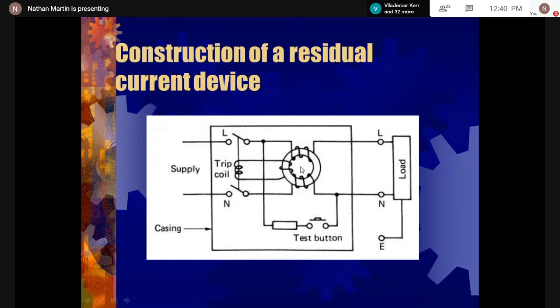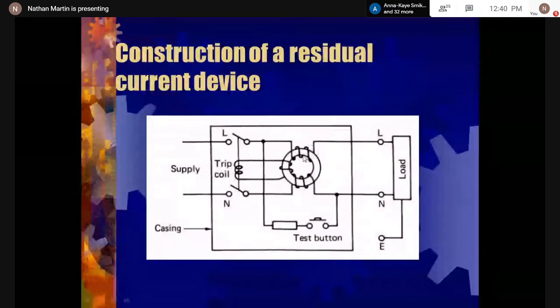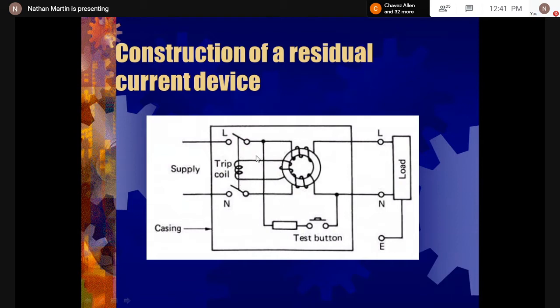Two coils, let me say it again, one with the current flowing in one direction, the other in the other direction. When the magnitudes are the same, the resultant is 0. There is no induced voltage. Now, if we have a short circuit to ground, then the current flowing into the device and the current flowing out of the device to the return, that's the neutral, will be opposite, but of different magnitude. Hence there will be a resultant, and that resultant will produce an induced voltage in the trip winding. Because it creates a closed path, you will have a current flowing. And this current, because of how it's designed with this solenoid, will operate the switch and cause the device to trip. Simple.